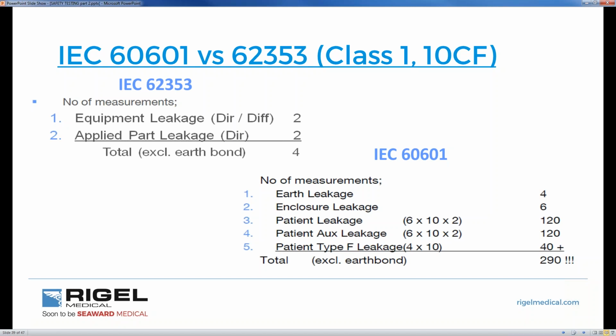If you have a hospital with 1,000 beds, then you're going to have a lot, and I mean a lot, of medical devices. So for your department that tests medical devices, time is critical: how you employ your staff, how your staff is allocated their work. If you're using 60601 to do your safety testing, as opposed to 62353, well, if I was to test a class 1 instrument with 10 applied parts, and the applied part was type CF, let's say for instance an ECG monitor, 60601 would require a total of 290 tests to be performed. That's going to take a lot of time to go through one test. 62353 does 4.